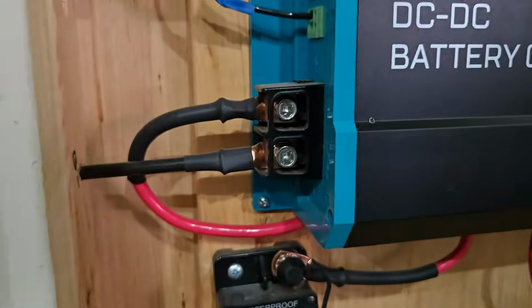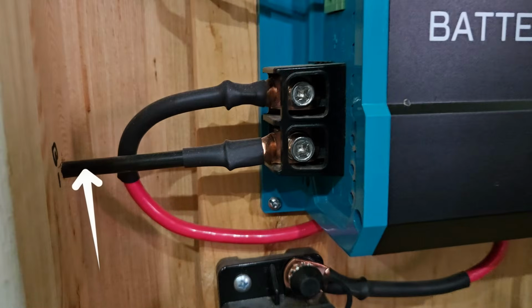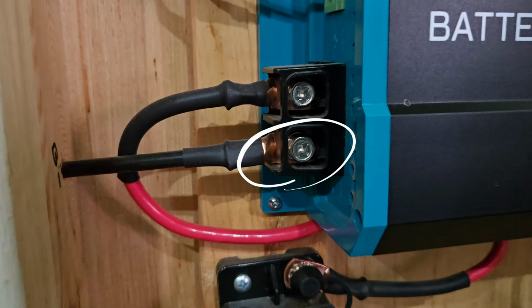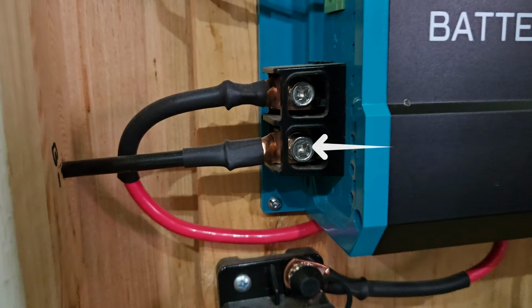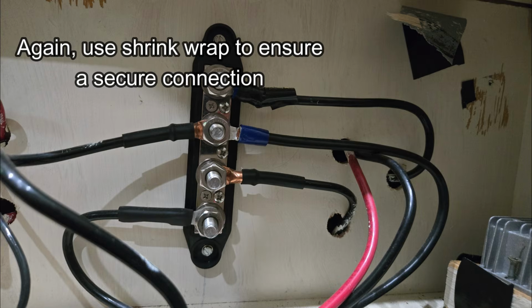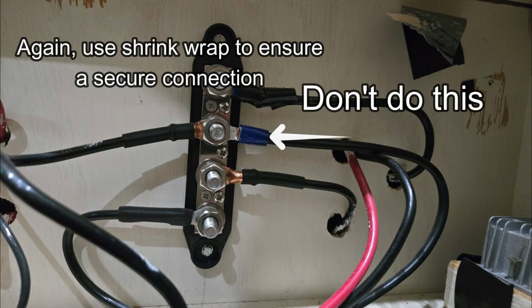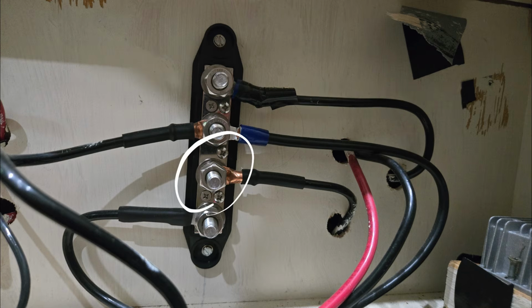Now for the negative wire, which is super easy. Strip one end of the negative wire and attach the appropriate size lug. Connect the lug to the negative output side of the charger, which is located below the positive output terminal. Tighten the screw to make a secure connection. Then, you just need to run the negative wire to your negative bus bar. Cut the wire at the appropriate length, strip it back, and attach a lug. Connect the lug to the bus bar with a washer and nut.